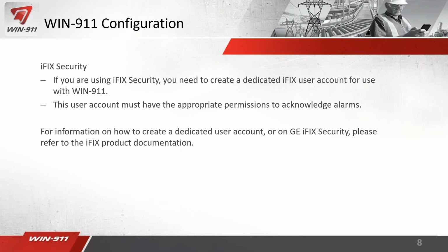Quick notes here about the iFIX security. If you are using it, you need to create a dedicated iFIX account for WIN-911. That's our recommended procedure, just because sometimes there's password change policies, or users can go in and out of being used for your iFIX side. So just create one that's dedicated to WIN-911 so the password never changes.